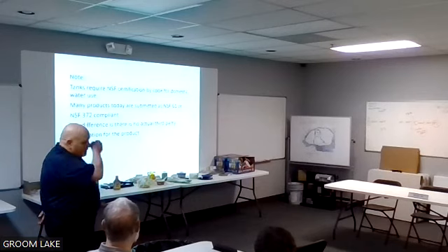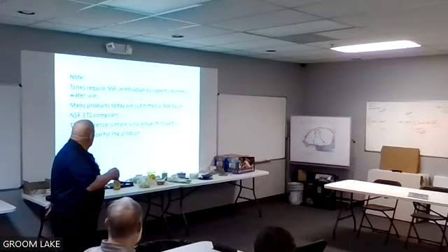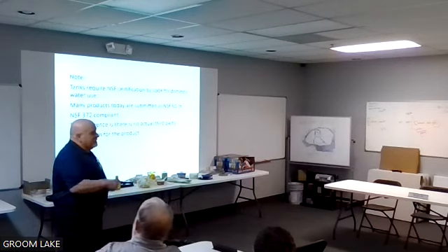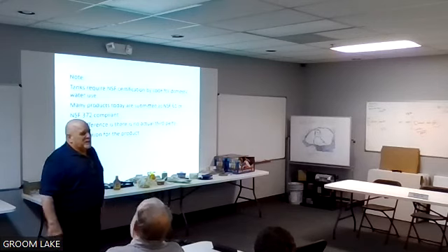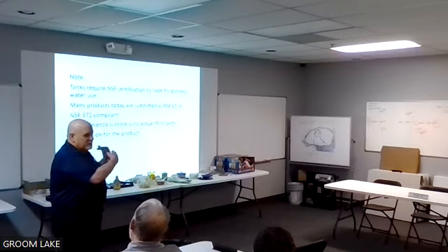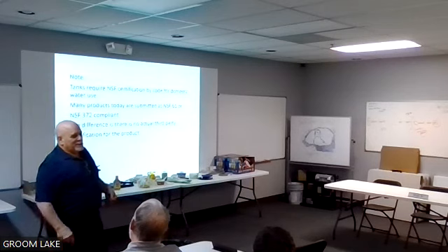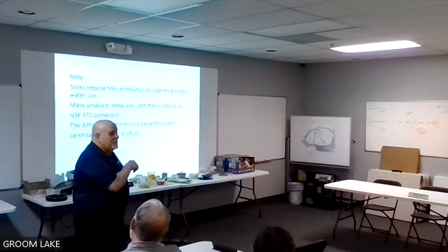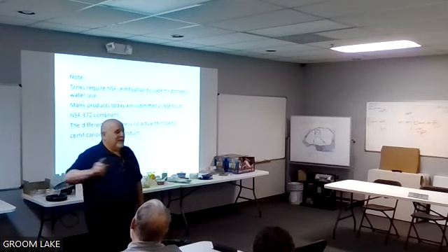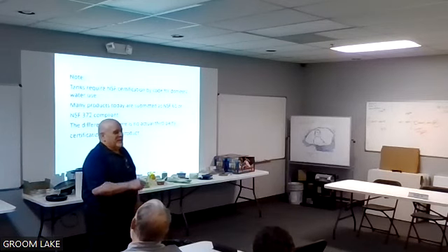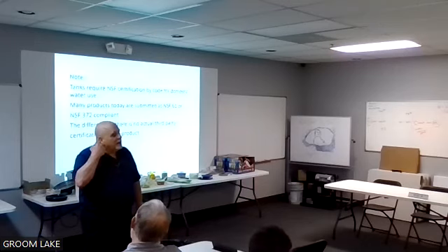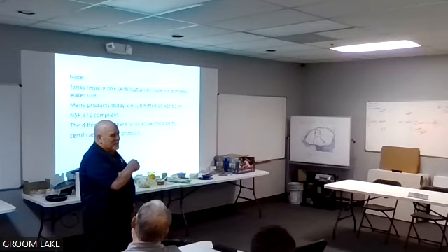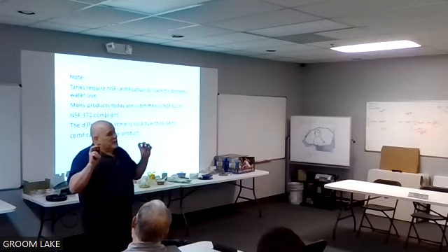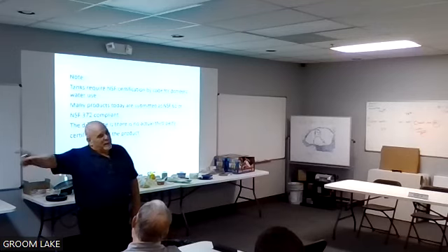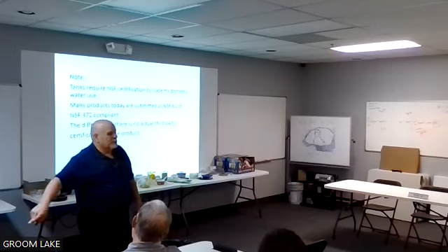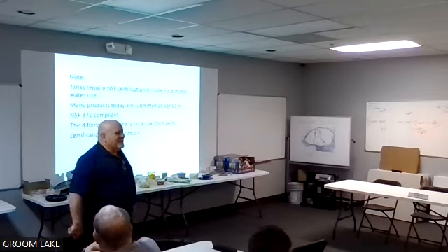A lot of times, be careful when you look at products. A lot of people, the new tag word is NSF 372 compliant. I'm NSF 61 compliant. The difference between my two tanks here: my standard PAX 30 is NSF 61 compliant, and my one with the certification is NSF 61 certified. So somebody tells you, is this lead free? Oh, it's compliant. You're taking a gamble. You don't have the paperwork. They're telling you all the material was built in accordance with NSF 61, but they didn't pay an inspector to watch them build it. They don't have a paper trail for it. So it gets kind of dicey.